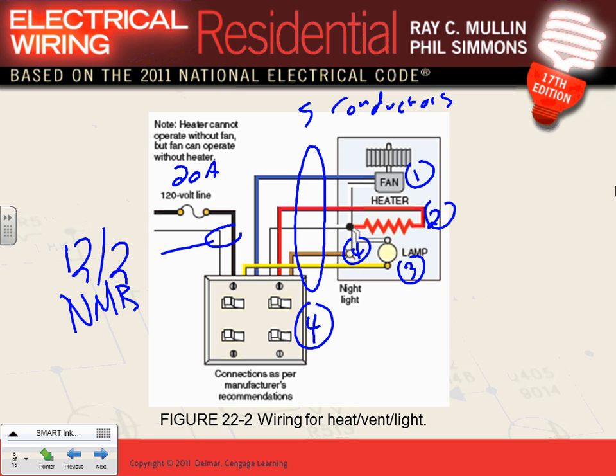So here, what would you do? You put a metallic box here, and would you use a flexible metallic conduit from here? So here's where you get the flex from here all the way, right? So you flex them, put them in a flexible metallic conduit, and you pull your conductor wires now into that fixture, and you pull your 5 conductors. Can you have thumbs up? We understand why we do this, flex it, because you can't find a 5 conductor in an NM cable. This will be 12-5. They don't make 12-5. They make 12-3 and 12-4, not 5, up to my knowledge anyway. You can MC, I believe MC, they can make them bigger than that, but they're not commercially available.